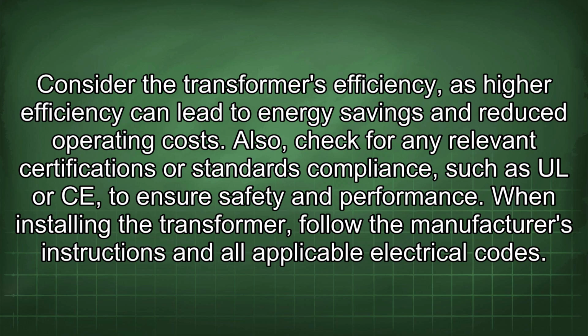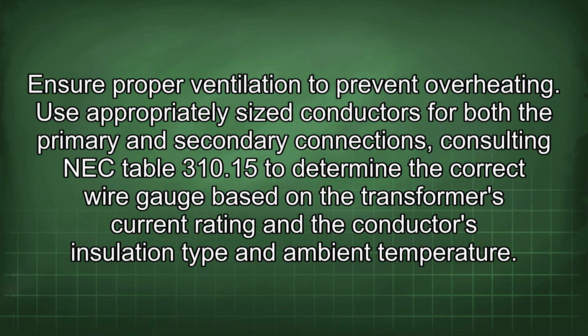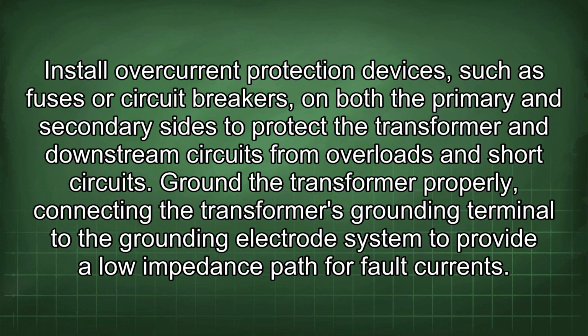When installing the transformer, follow the manufacturer's instructions and all applicable electrical codes. Ensure proper ventilation to prevent overheating. Use appropriately sized conductors for both the primary and secondary connections, consulting NEC Table 310.15 to determine the correct wire gauge based on the transformer's current rating and the conductor's insulation type and ambient temperature. Install overcurrent protection devices, such as fuses or circuit breakers, on both the primary and secondary sides to protect the transformer and downstream circuits from overloads and short circuits.